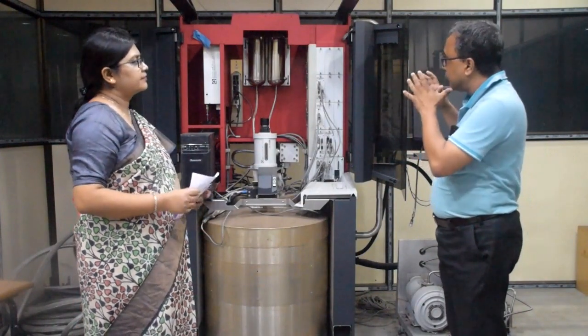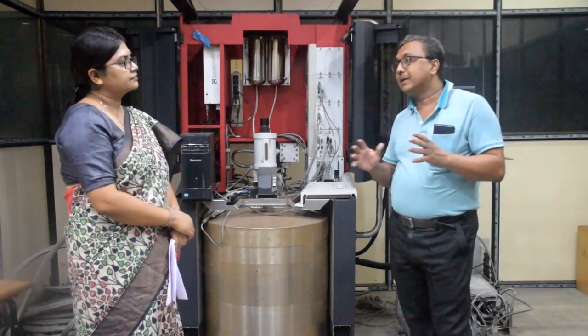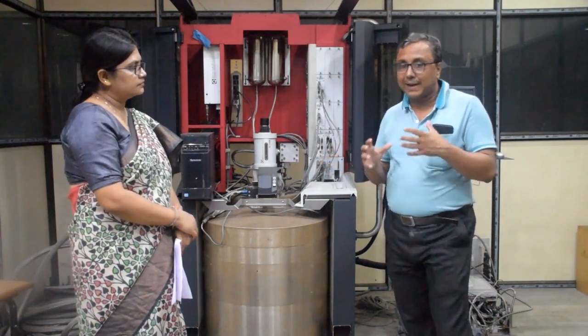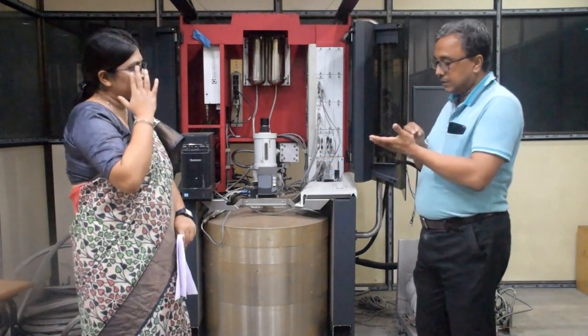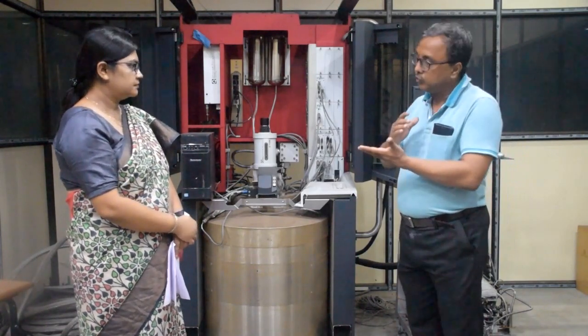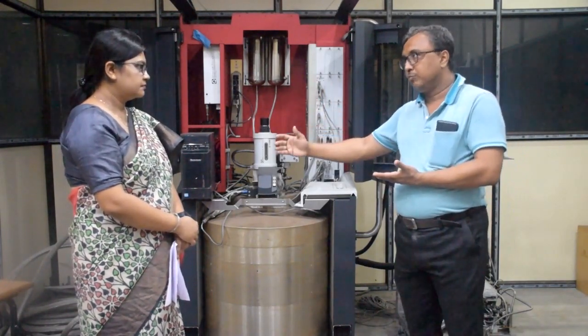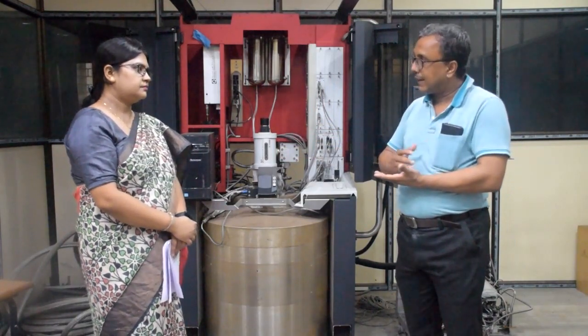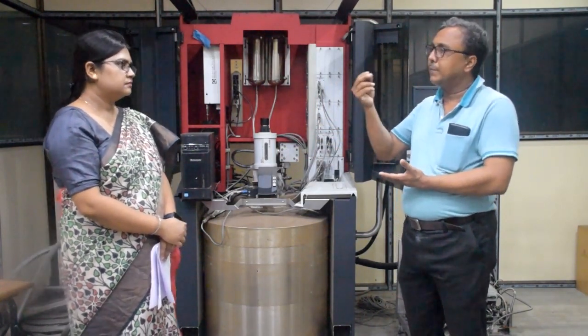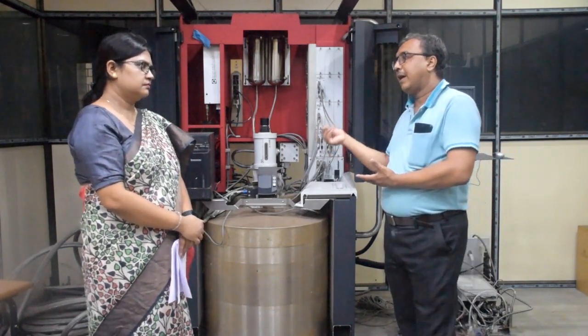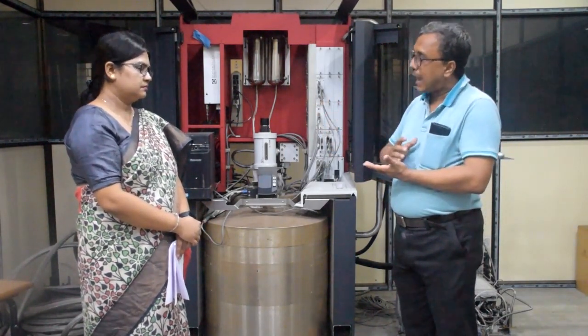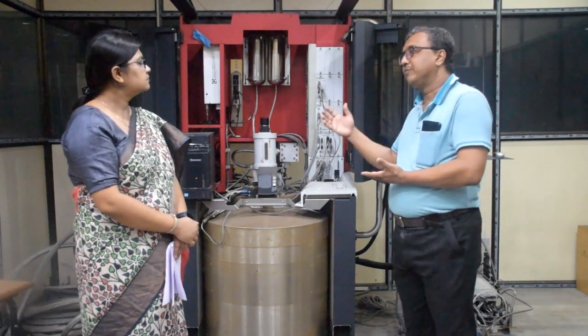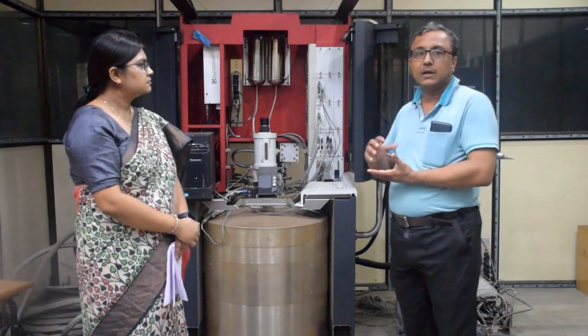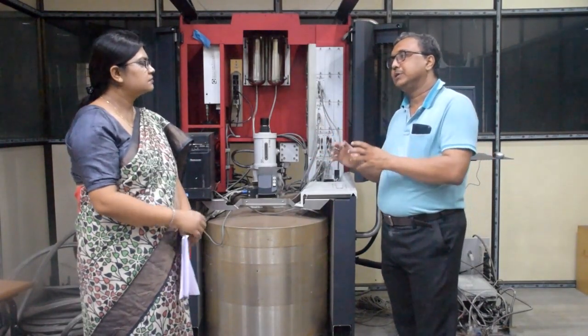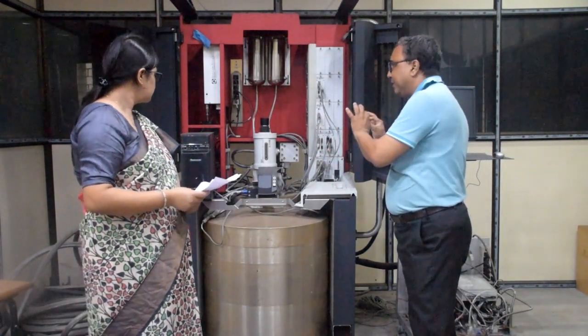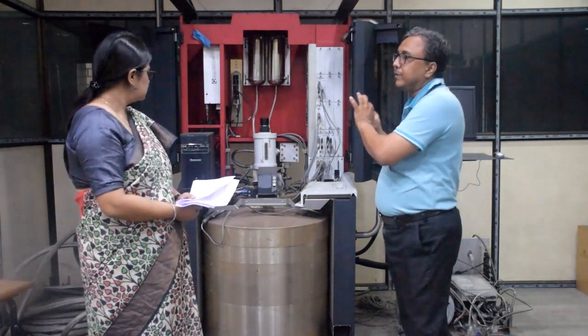So as I told, this is one of the most sophisticated instruments for measuring the magnetic structure, magnetic phase, and magnetization of a material. It can scan from 2 Kelvin to room temperature, 300 Kelvin, and it can detect any change in even a very small amount of magnetic moment. It is a very sensitive instrument, and over temperature change and field variation up to 12 Tesla, you can check the change in the magnetic property of the system, even a very feeble magnetic moment.